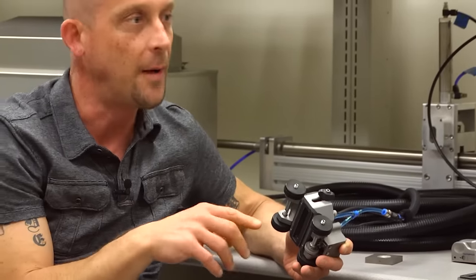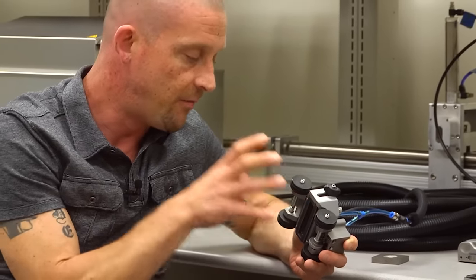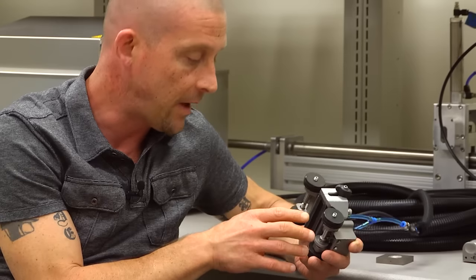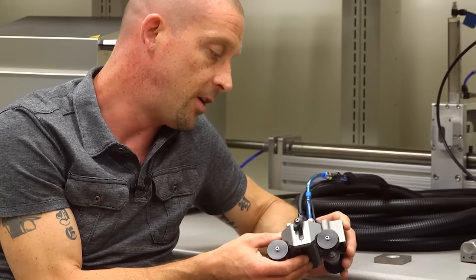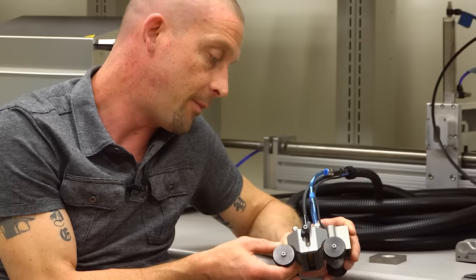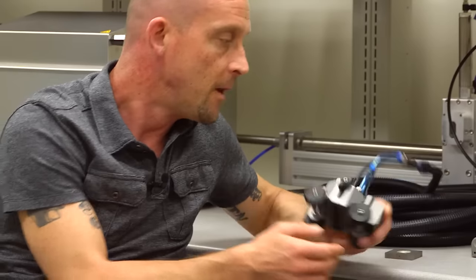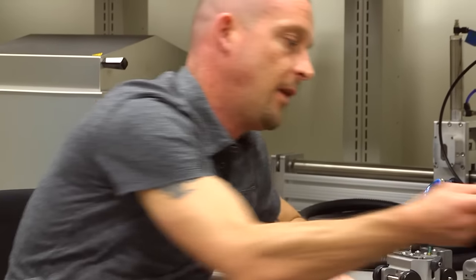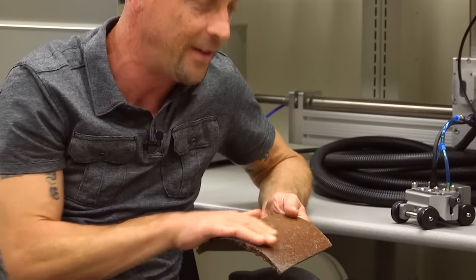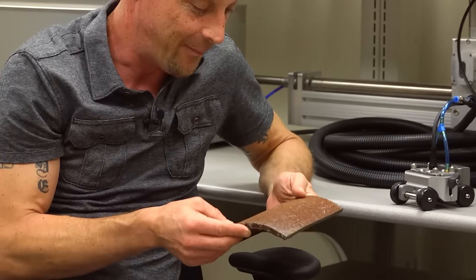For example, the HydroFORM is water based—we use water as the couplant. It has different sealed gaskets depending on whether we're going around the circumference of the pipe, and we can swap plates to form a seal using water as the couplant path. The advantage of this solution is that it can be hooked onto scanners for very rapid XY scanning, either automated or semi-automated. The real benefit of using water is that sometimes the condition of the metal isn't always like it comes out of a manufacturing plant—it has varying amounts of surface irregularity, so we still want to UT prep it a little bit.